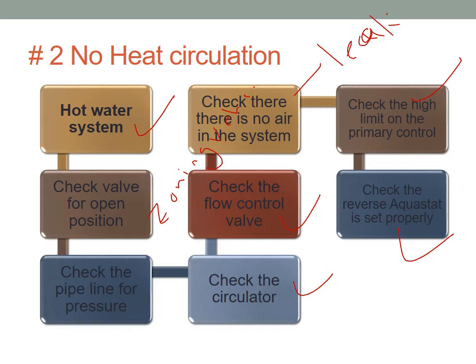So check the high limit and check the reverse aquastat that is set properly, that the high and low limit are working okay. And again, when you do a hot water system and you do some checks, make sure it shuts off at high limit and turns on the pump at the low limit. So again, this is to check our circuit.